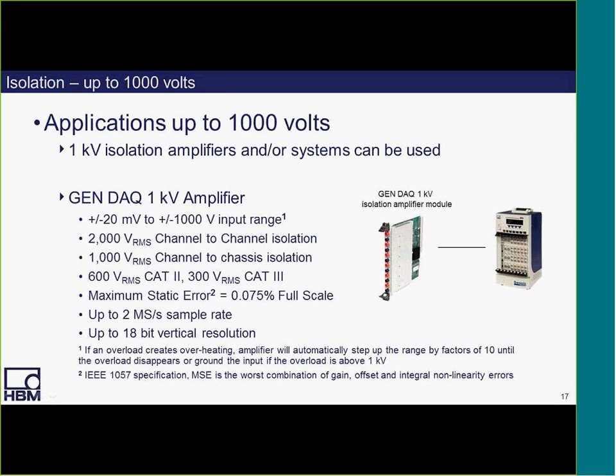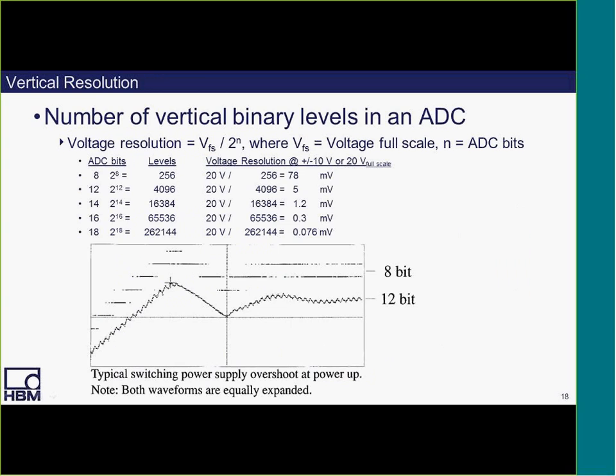In addition to that, the isolation channel to channel on this amplifier is 2,000 volts RMS, and the channel to chassis isolation is 1,000 volts RMS. The Cat 2 specification is 600 volts RMS, Cat 3, 300 volts RMS, and the maximum static error, which happens to be IEEE 1057 specification, the worst combination of gain, offset, and integral nonlinearity error, is 0.075% full scale. It's a rather impressive specification. You can sample up to 2 million samples per second on every channel and achieve a vertical resolution of up to 18 bits. In fact, speaking of vertical resolution, this next slide clearly shows the importance of high vertical resolution. The diagram is actually the result of an experiment I did many years ago.